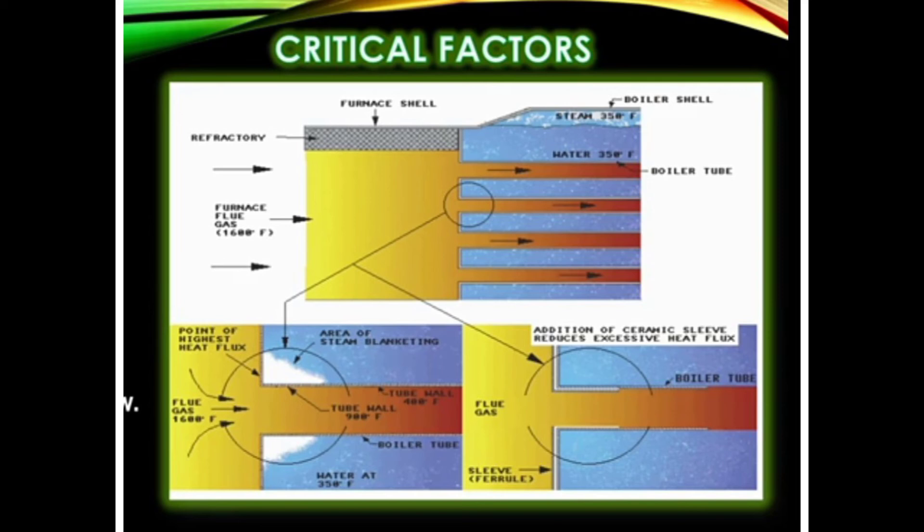Another reason for steam blanketing may be a disturbance in water flow or disturbed water circulation. If your water circulation is not proper and you have stagnant water at any part of the boiler tubes, this will also cause steam blanketing.